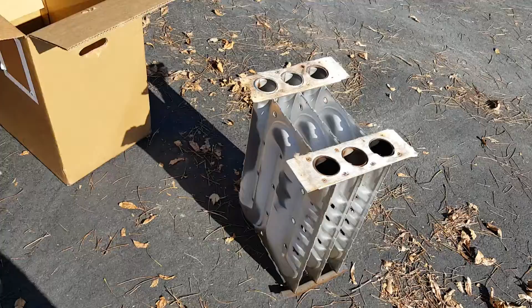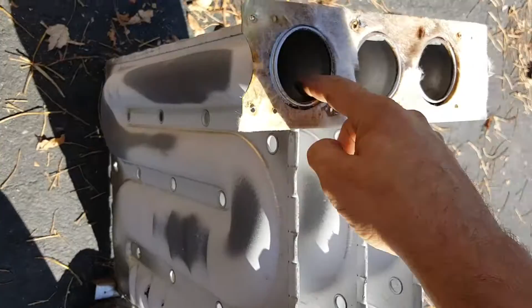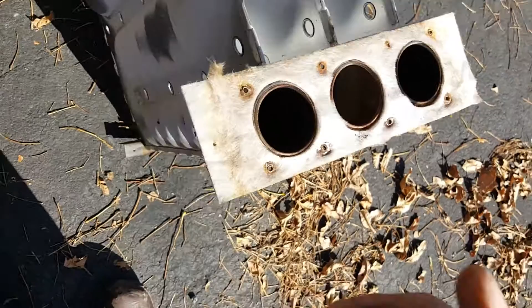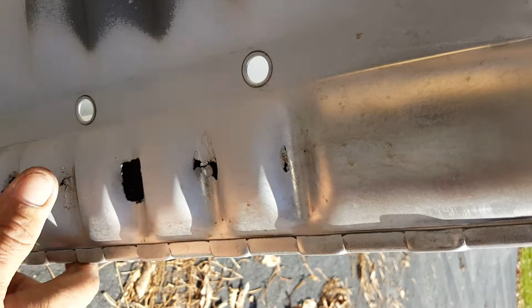This is a primary heat exchanger out of maybe an 11-year-old furnace. This is where we fire into it, and this is where it leaves the exchanger to go into the secondary. These are all the holes in the heat exchanger that were leaking products of combustion into the house.